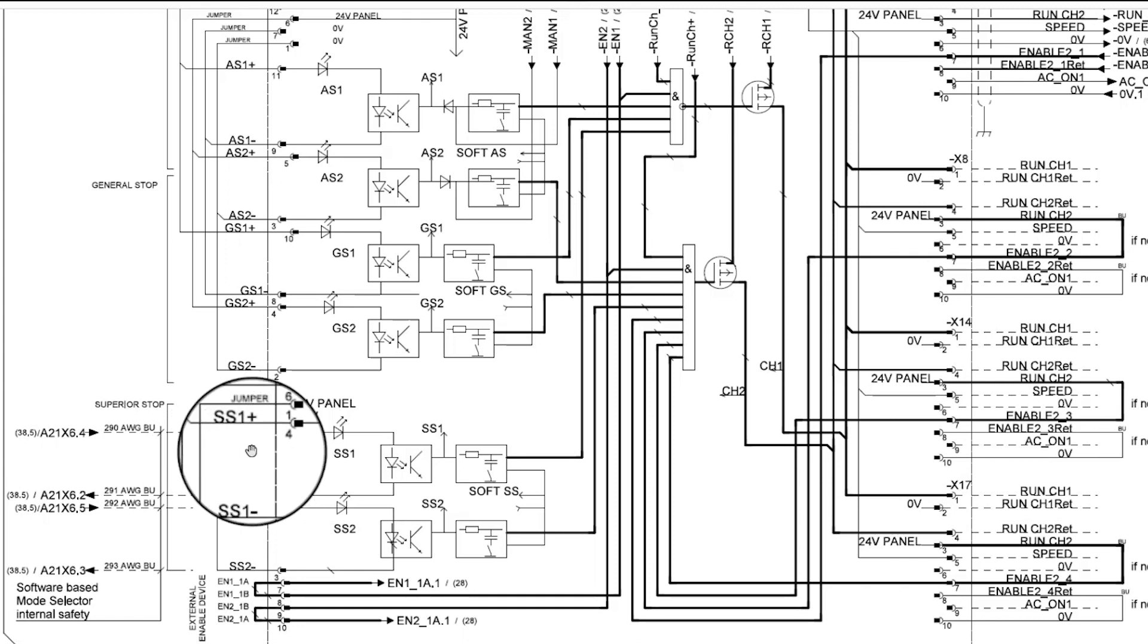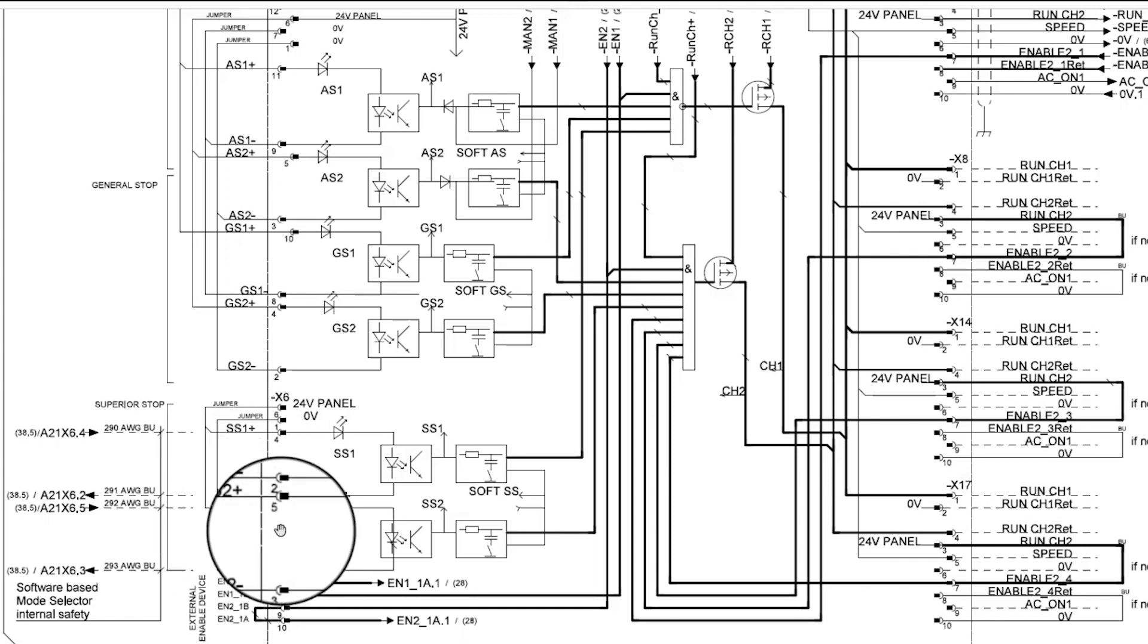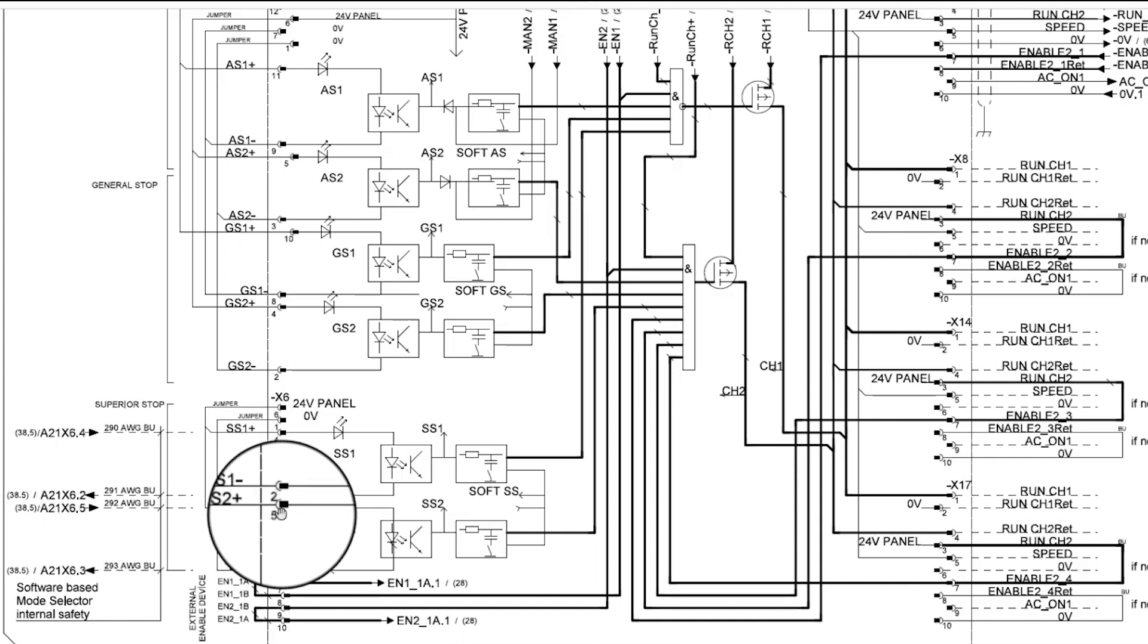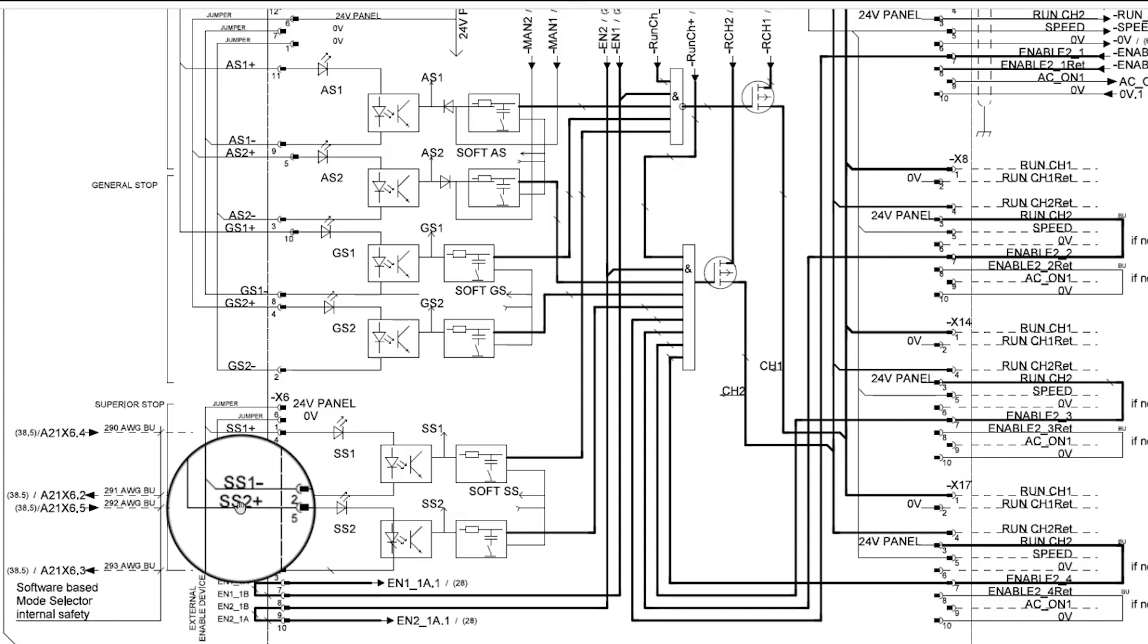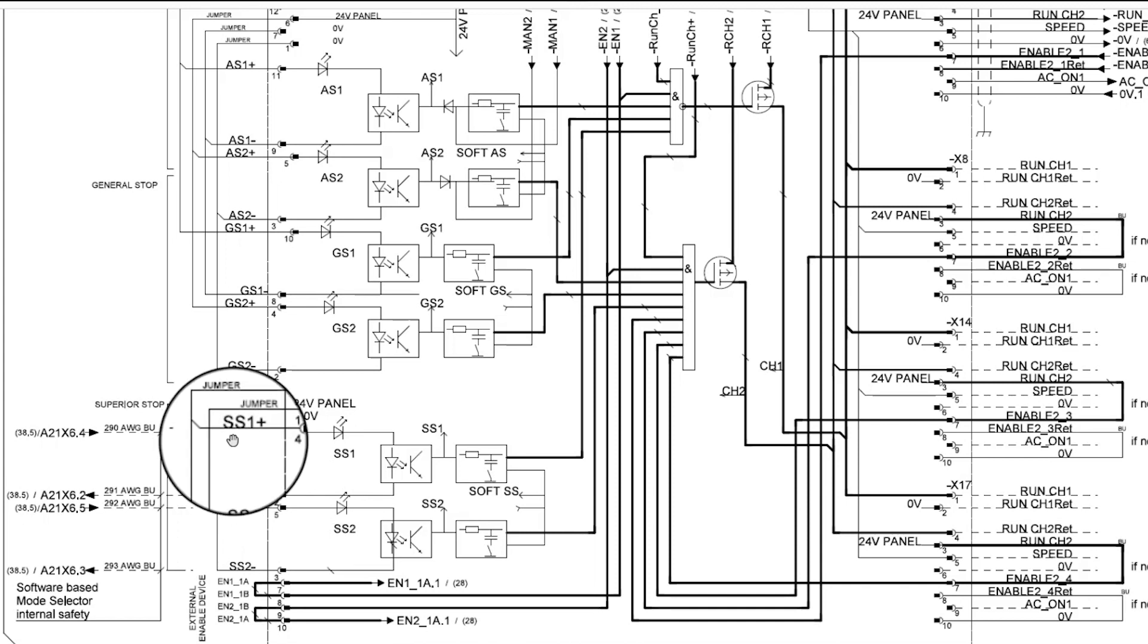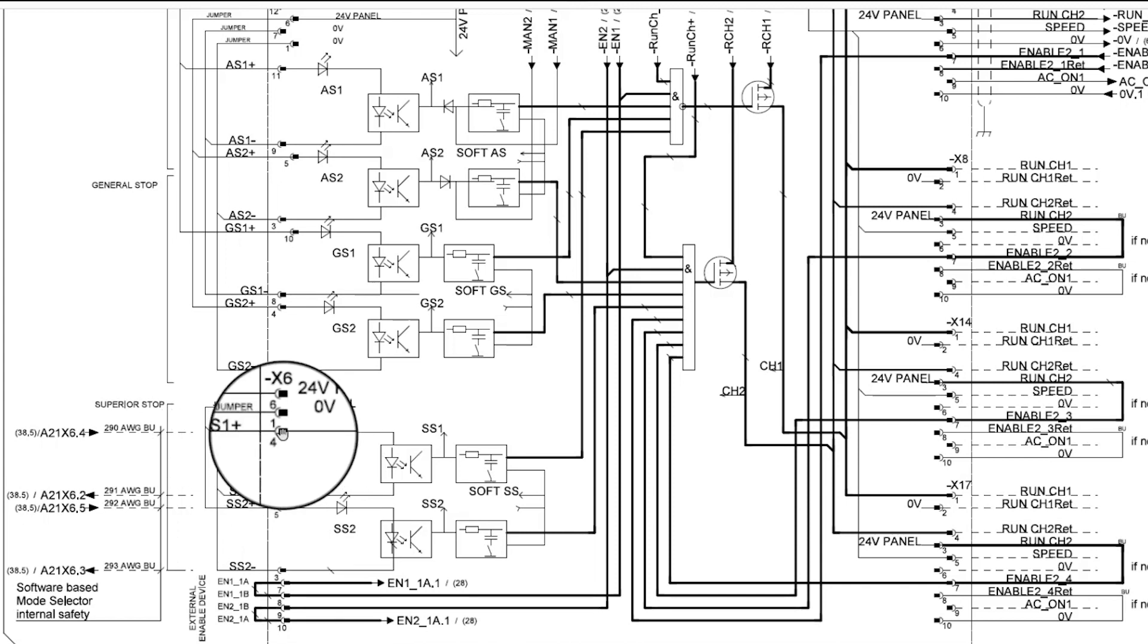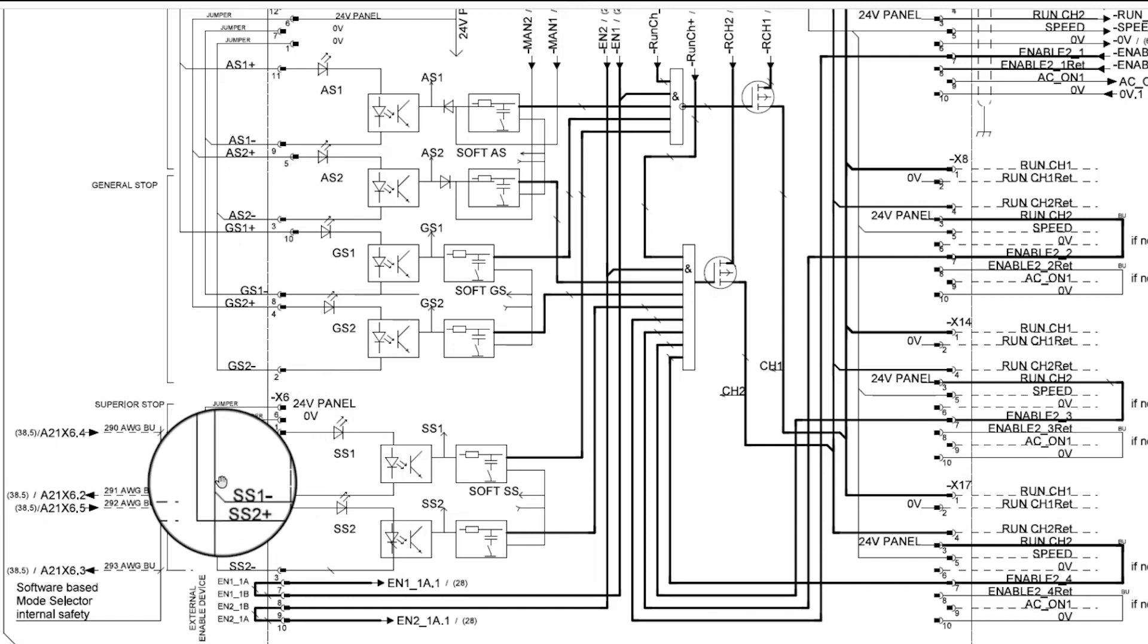Now that we know where SS1 positive gets its 24 volts from with the factory jumpers installed, let's take a look at SS1 negative or 0 volt and where it's located on connector X6 position 2. As you can see in the circuit diagram there is a very similar factory jumper installed in positions 1, 2, and 3 which position 1 is the 0 volt supply from the panel board.